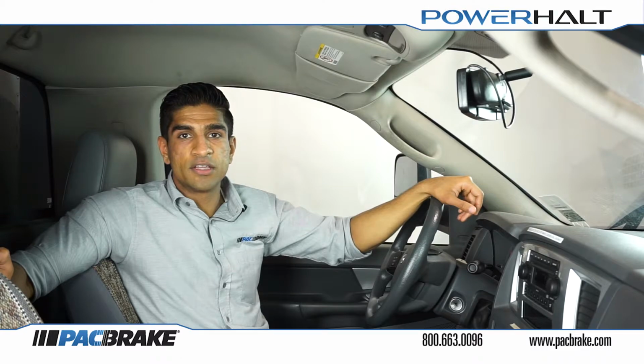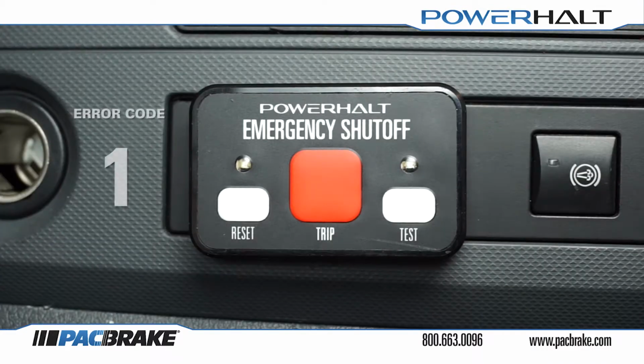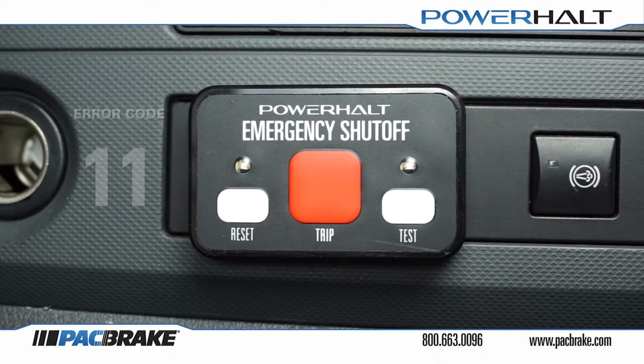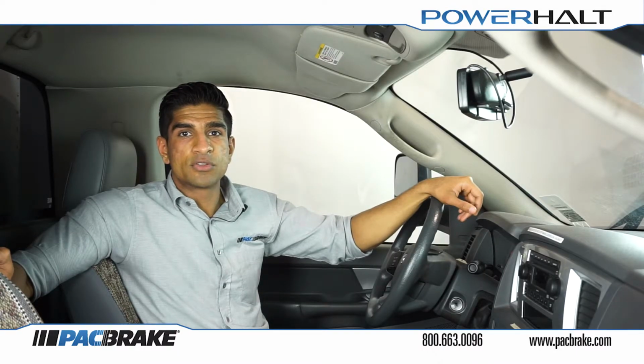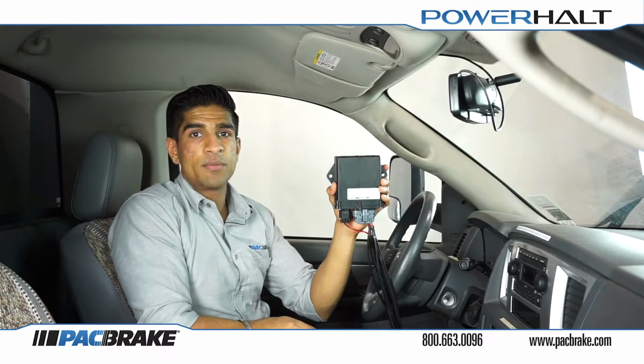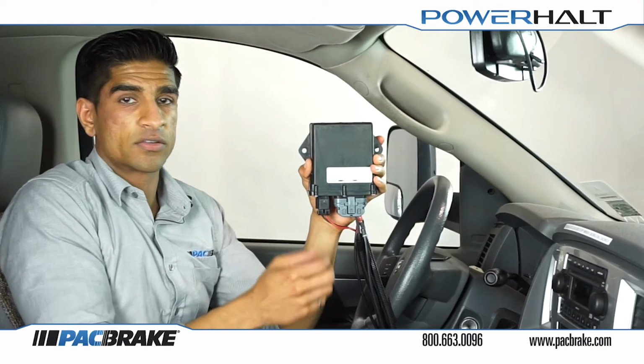In this particular case, the system is showing 11 simultaneous flashes. This corresponds to error code 11, which indicates that the valve motor is disconnected. Code 11 is most commonly due to the 2-pin connector not being fully seated and locked to the control module. When the connector is not fully seated and locked, it can become loose due to vibration and then become disconnected. To remedy the issue, we must securely connect the 2-pin connector until it clicks and locks.